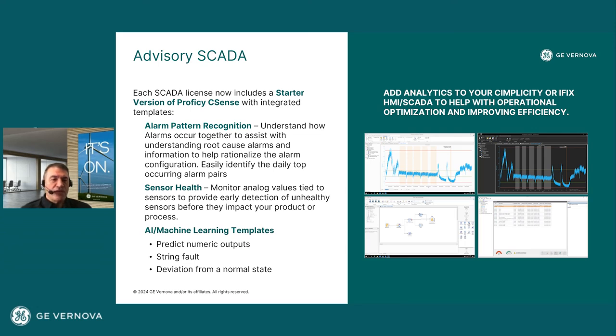The concept here is, can I start determining which alarms are actually happening at the same time? Meaning, when this alarm occurs, these other three things always happen. Start being able to pick up on those patterns so it helps you look at things like root cause alarms, or even rationalize your alarm system by making sure only the alarms that matter show up for the operators.